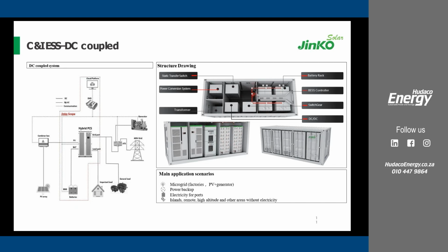Control for the generator is done because the PCS is intelligent. What we currently do is basically remote start/stop for the generator based on set conditions. One condition is the state of charge of the battery - for example, you can set the generator to start at 20% SOC and it will automatically start. Another condition is peak shaving mode, where you can set the time at which you want the generator to charge the batteries. So it will automatically start under such conditions.